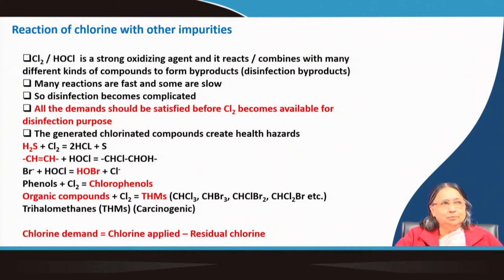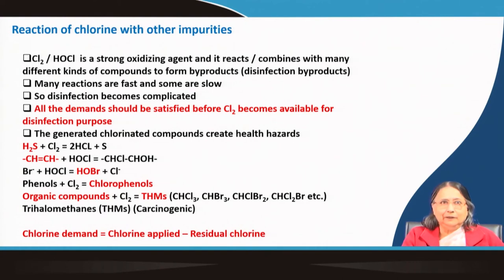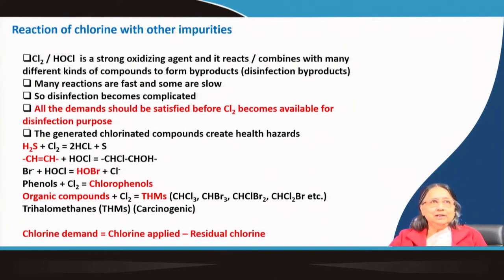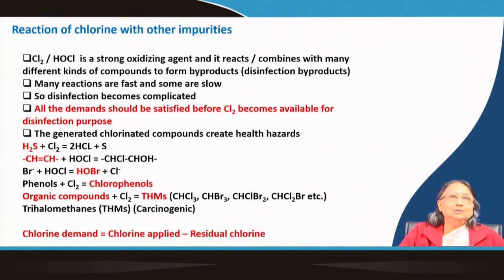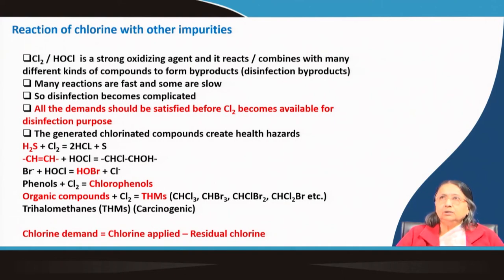Unless the chlorine demand is met, we will not get free chlorine to kill bacteria. Those compounds must first satisfy their demand, and after that we get chlorine for disinfection. The generated chlorinated compounds can also create health hazards. In groundwater, H₂S or sulphide salts may be present because water leaches through sulphide-bearing rocks. H₂S gas can react with chlorine to form HCl and sulphur.